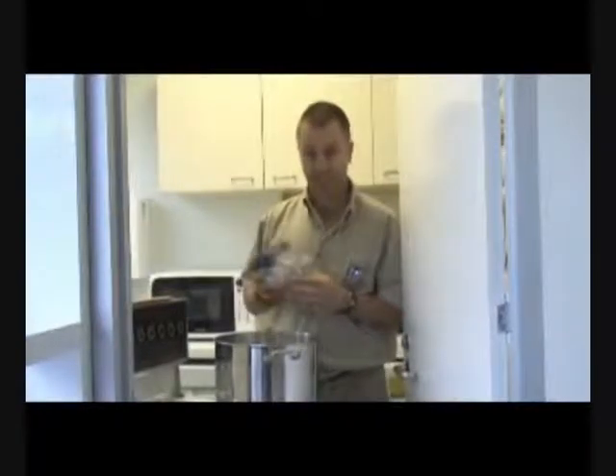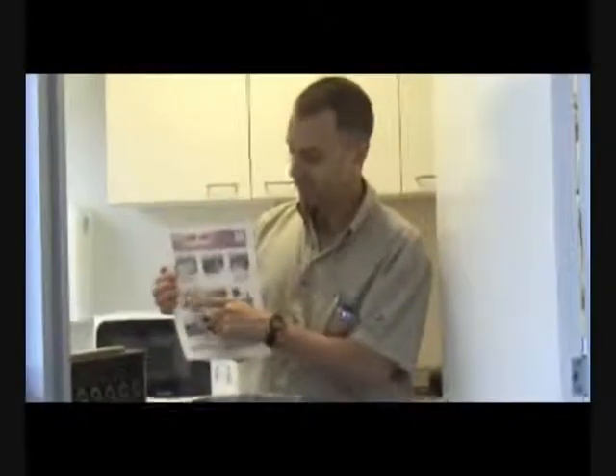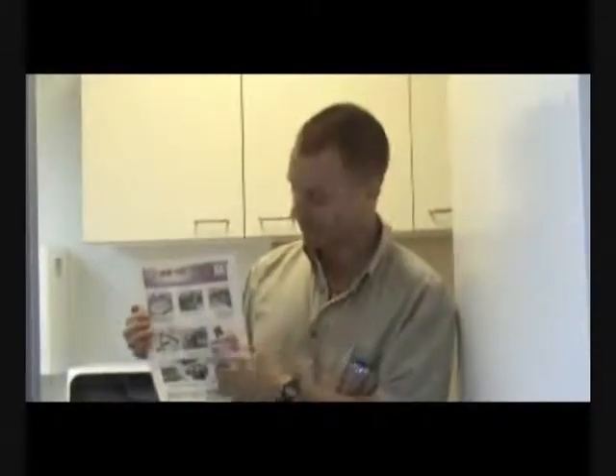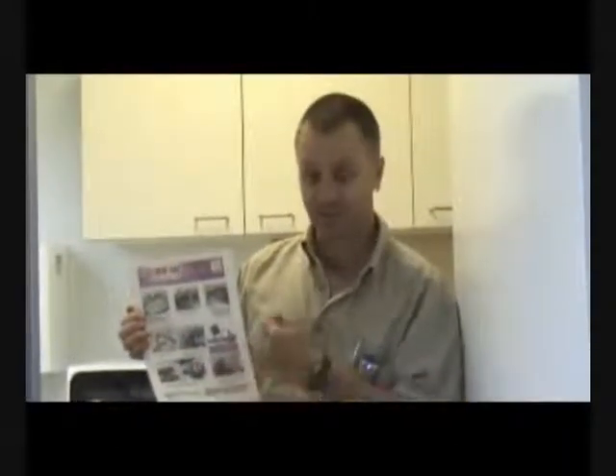So that's the procedure on how to sterilise the instrument. As I said, it's on our website. So when you're sterilising, if you have an applicator that uses a feed tube, attach the feed tube to the applicator, and then pump some water into the applicator, get the water into the barrel before you start boiling it. There's a picture here that shows you what happens to an applicator if it touches the bottom of the pan. So if it touches the bottom of the pan, that's the hottest area, it will damage the applicator. And then we suspend the instrument, boil it, and then use the cloth to remove it out of the water as I showed you, because the instrument's going to be very hot.